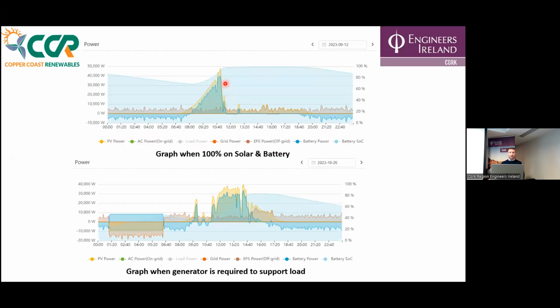And then the solar reduced, even though the solar could produce 50 kilowatts at 11 a.m. It could continue to produce 100 kilowatts, but the on-site load doesn't need it. So we can't just pump 100 kilowatts into a place that isn't going to use it. That's called export limitation. We then reduce the solar capacity via the inverters to match the on-site load. So that's why you see down here, you can't see the yellow because it's matching the on-site load, just a slightly different color to what the load is.